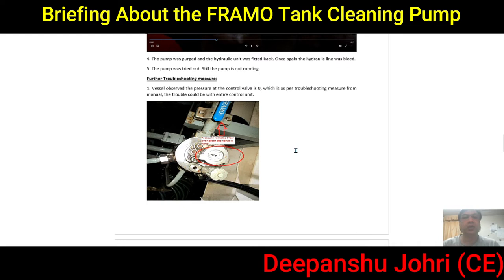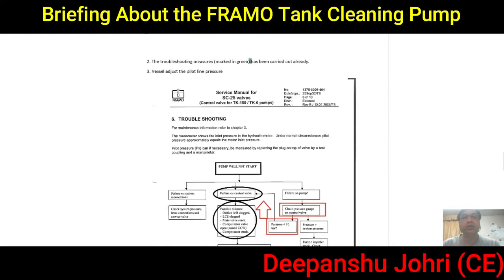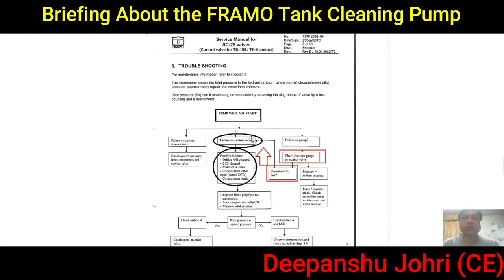We decided to investigate the hydraulic side. Looking at the troubleshooting chart with green marks showing completed checks, we needed to check the pilot line pressure. According to the chart, possible causes for control valve failure include a clogged orifice, clogged LCS, stuck main block, or a compensator valve open and turned counter-clockwise. The compensator could also be stuck — any of these things could have gone wrong.